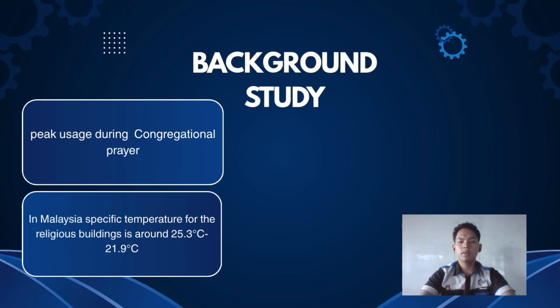Looking deeper into the background, religious places like mosques and surau in Malaysia present a highly unique operational pattern compared to typical office buildings. They experience intense, sudden peak usage during congregational prayer times, which creates an immediate spike in internal heat and moisture production from the worshippers. Currently, the majority of religious buildings manage their indoor environment using a combination of split-unit air conditioners and mechanical fans, including wall-mounted and pedestal units.